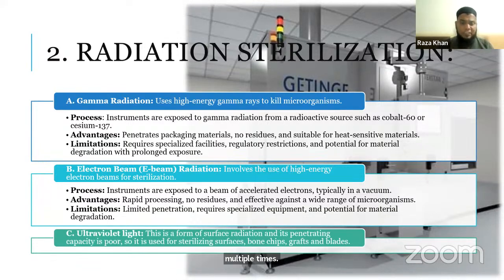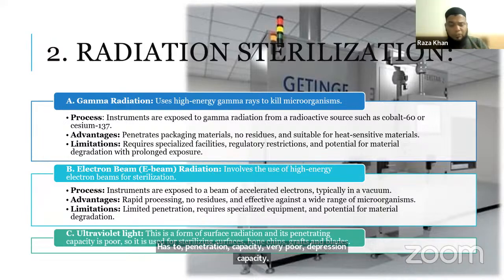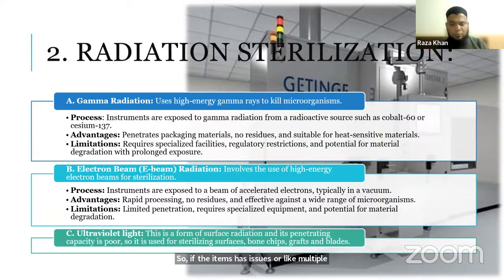An example of a non-ionizing radiation method is the use of ultraviolet light. Commonly we use UV light for environmental disinfection, for theater disinfection, and in commercial or non-commercial use, people usually sterilize bone chips, grafts, and blades through the UV light method. But this is not a very good method because it only disinfects the surface. It has very poor penetration capacity. So if the items have residues or multiple layers, then this method would not be effective.